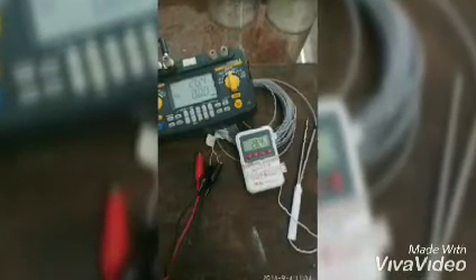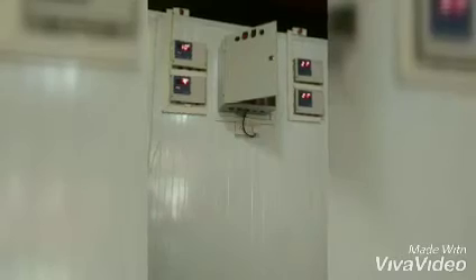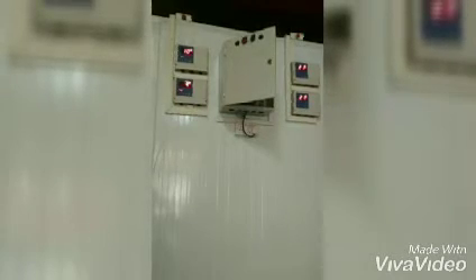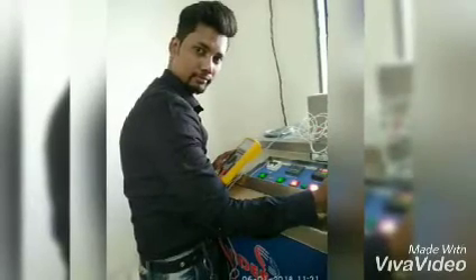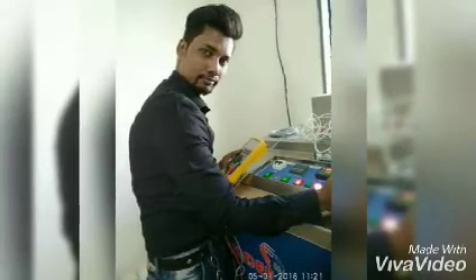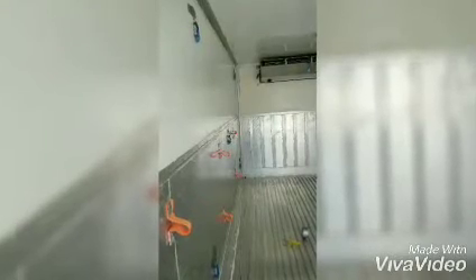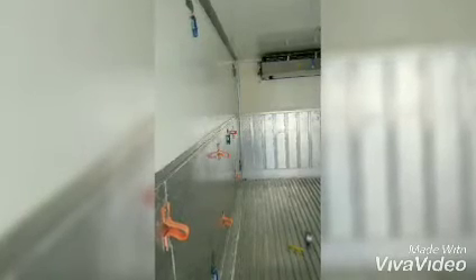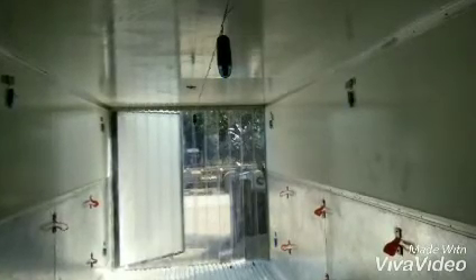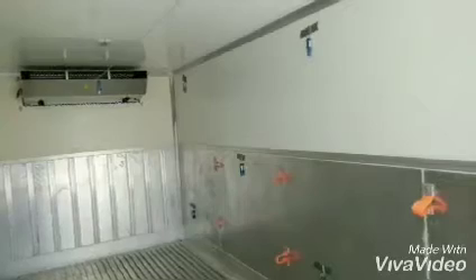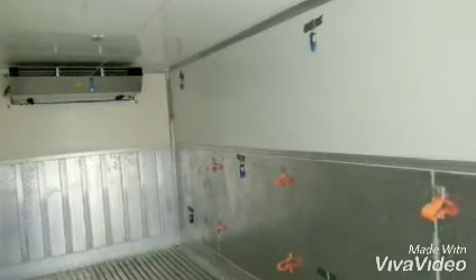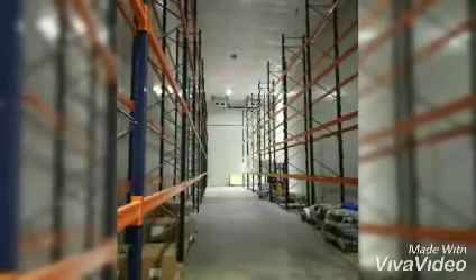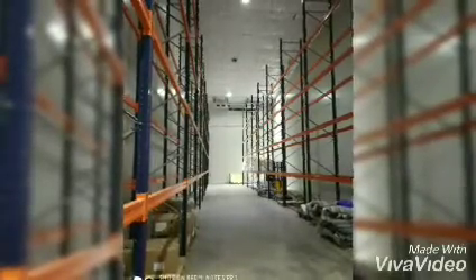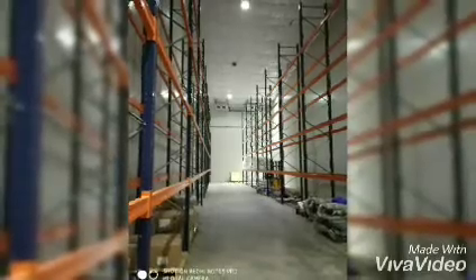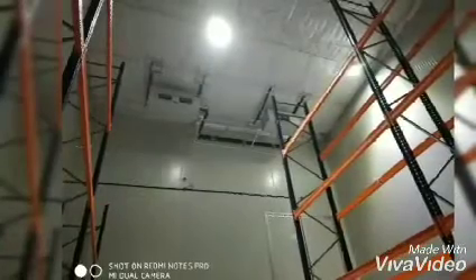After successful completion of the OQ cycle, our VEGA engineers proceed with the performance qualification study, which is also known as the load cycle test because the temperature mapping study is performed in a loaded storage area. During the PQ study, the position of the wireless data loggers is kept the same as in OQ. This continuous cycle test study is to be carried out again for 24 hours, 3 days or 7 days depending upon the client protocol. After the continuous cycle test is performed for operational qualification and performance qualification, recovery tests such as the door open test and power failure test are performed.